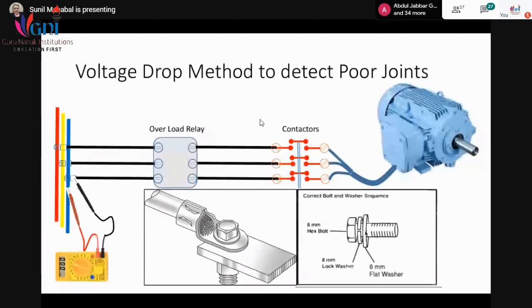And once we tightened that and provided the bimetallic washer, which we had to buy from the market, we replaced all the washers on that bus bar, and then we finally fitted it, and thereafter the motor never tripped. So this small voltage drop occurring because of the lug and bus bar connection was resulting in single phasing, which actually should trip when there is absence of one phase. But this is not absence of one phase. This is just reduction in voltage of one phase. But even that was sensed by the single phasing relay as absence of one phase. Therefore, it tripped. So this is how the problem was solved.